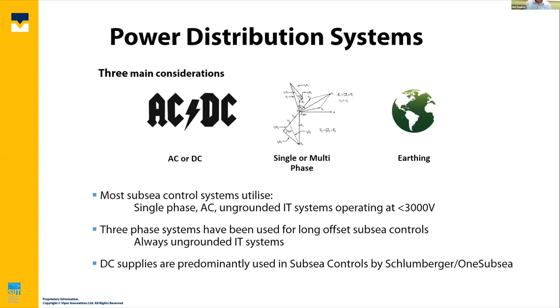When you have long offset umbilicals, cables, and when I'm talking long offset, probably beyond 60 or 70 kilometers, you will typically see the subsea controls providers going to three-phase AC systems, but again, it is always an ungrounded IT earthing system that is utilized. And then a final bullet point there, for those who are familiar with the old OneSubsea or Schlumberger controls out of Celle, they are typically supplying DC systems, so they're all electric tree, and their subsea control systems are typically DC supplies.